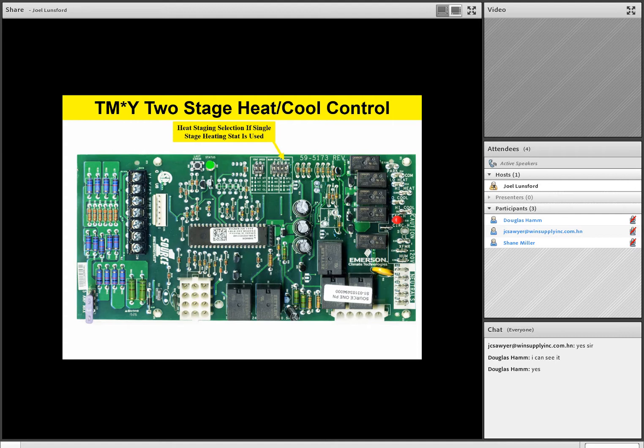Likewise, if it's in the 20-minute position, on a call for heat it'll run 20 minutes on first stage on a W/W1 call. And then if you still have a heating call after 20 minutes, it'll go ahead and bring on second stage heating to finish that call. The last option is what we call auto. If the dip switch on the left-hand side is down and the dip switch on the right is up, that's the auto position.